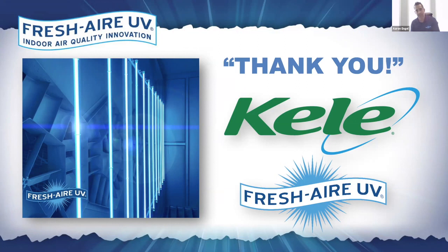So you get that drain pan. Because yes, if you put a UV light on the upstream side, that light will not make it down into the drain pan. So mount the lamp as the sizing recommends on the downstream side, and then maybe put a few lamps, or a booster lamp so to speak, on the upstream side if we need to get that full penetration through.